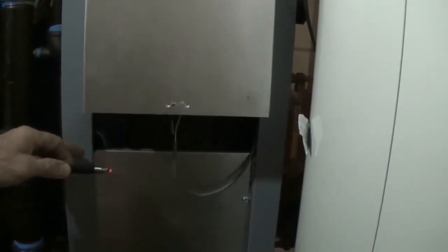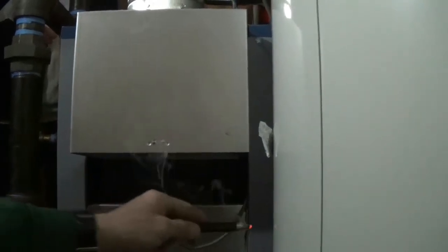I can tell you I've done the combustion safety testing in this house a number of times, and this thing does fail spillage under worst case conditions. Now, same thing with this. Would you be moving the smoke stick and trying to see if it passes on all sides? I would, absolutely. But I saw it failed one place, so I know it fails because it fails anywhere. Once it fails, it ultimately fails. Yep. But you do give it the full 60 seconds.